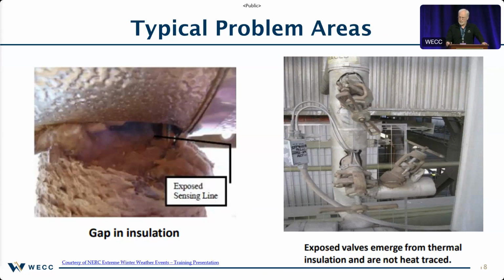This is some examples. This is a gap in insulation. When you're talking about critical sensing lines to power generators, especially any small gap in that insulation can allow that cold weather to get in, you get that one blockage of ice that blocks that control line, and you can adversely impact the ability of that generator to produce the power. The other one over there, exposed valves. So they have thermal insulation there, but it's not covering all of the equipment.